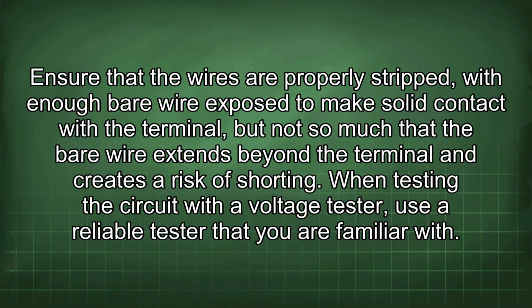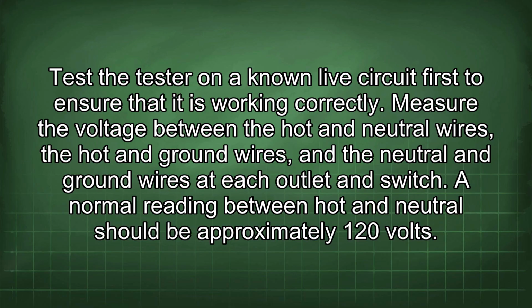When testing the circuit with a voltage tester, use a reliable tester that you are familiar with. Test the tester on a known live circuit first to ensure that it is working correctly. Measure the voltage between the hot and neutral wires, the hot and ground wires, and the neutral and ground wires at each outlet and switch.